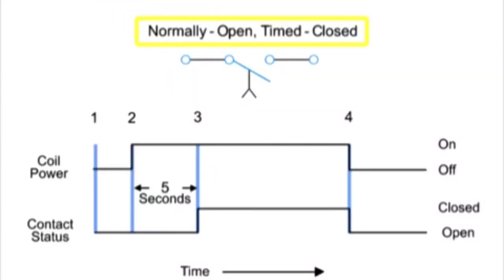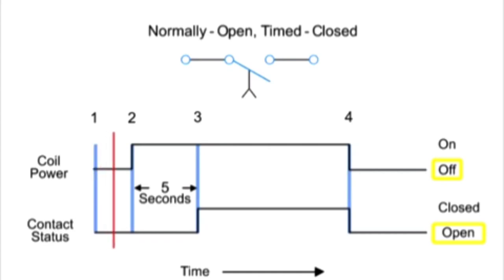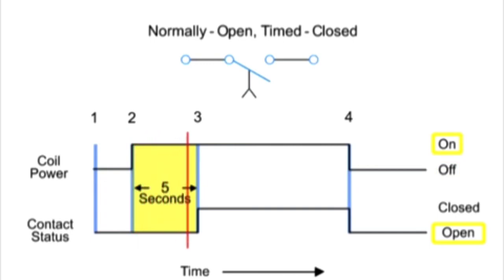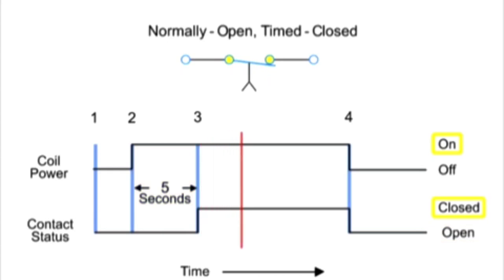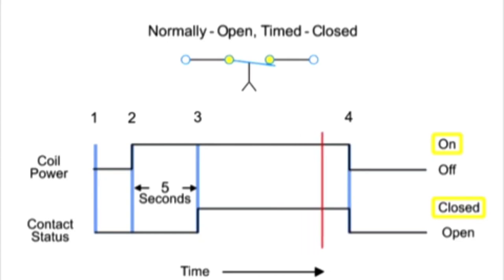First, we have the normally open, timed closed — NOTC — contact. This type of contact is normally open when the coil is unpowered or de-energized. After the coil has been continuously powered for a specified amount of time — in this example, five seconds — the contact is closed. The contacts will immediately open when the coil is de-energized.